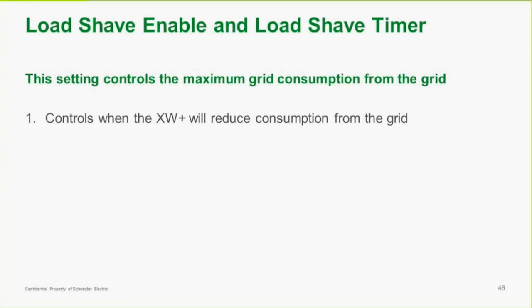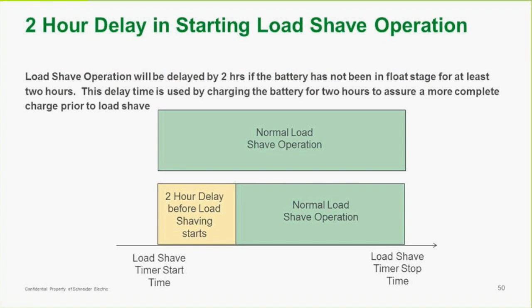Load shave enable and load shave timer control the maximum consumption from the grid and when the XW Plus will reduce consumption from the grid. So again, you can set that up so that when you have the highest cost of electricity during the day, that's when you're going to do load shave. And you can set the load shave timer to be more specific about the time of day. You can add a 2-hour delay before load shaving starts. If the battery is being charged and has not been in float stage, that 2-hour delay will allow the battery to become fully charged before load shave action begins.